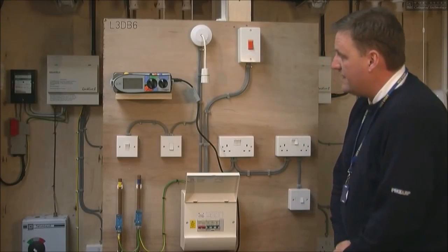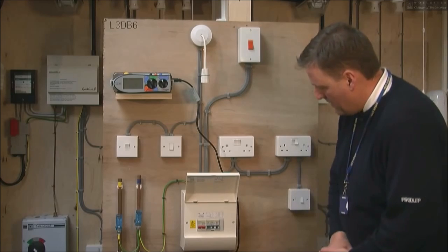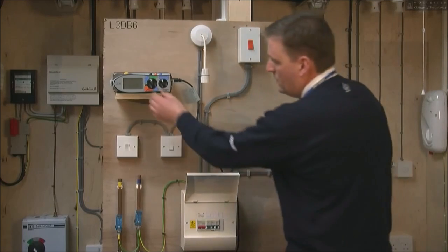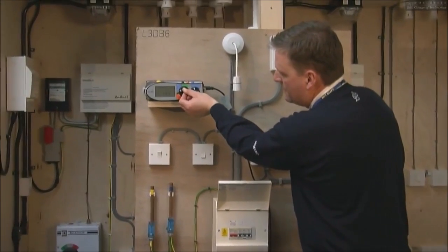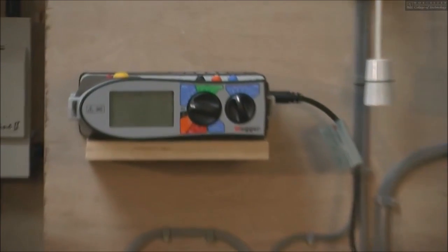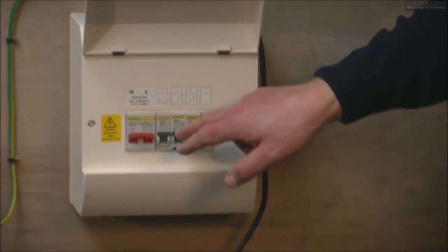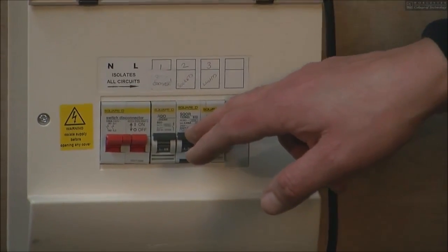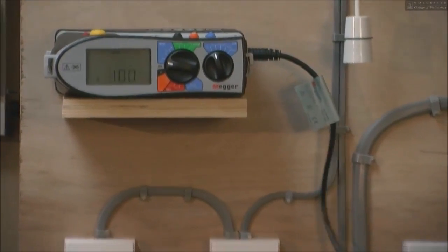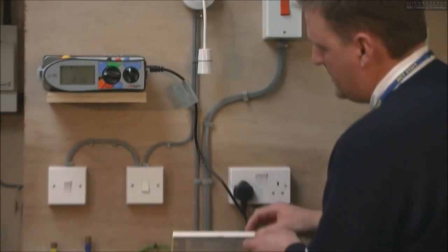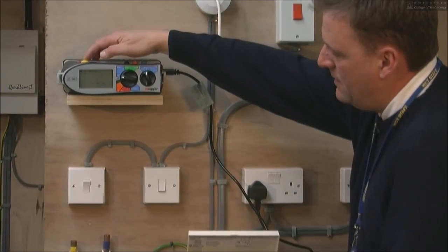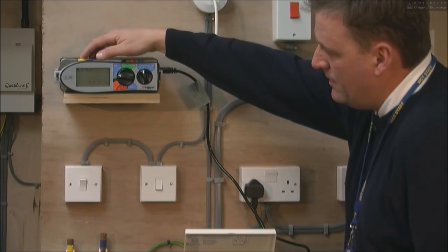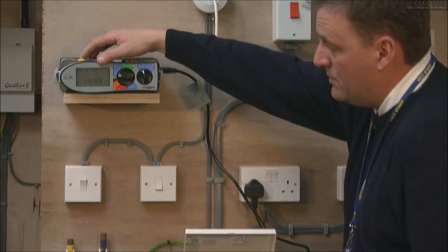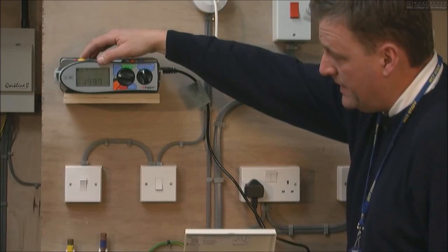The next test is the RCD test. We're going to actually test the RCD of the circuit now on the sockets. So we set the tester to RCD on the half test. We look at the protected device and it actually says 0.03 amps, which is 30 milliamps. So we set the tester to 30 milliamps. We then plug the tester in, and on the half test we press the button. So there's now testing at 15 milliamps, which in theory shouldn't trip the RCD.